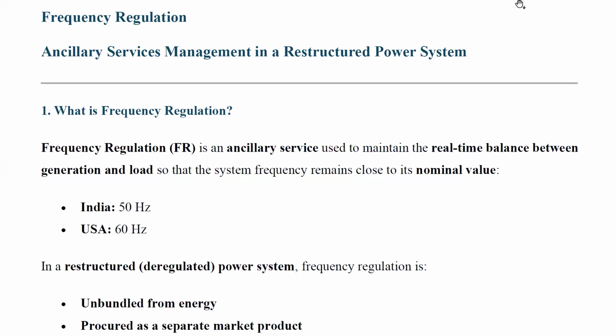Today we are going to see about frequency regulation, which is one of the ancillary service managements in a restructured power system. So, what is meant by frequency regulation? Frequency regulation is an ancillary service that is used to maintain the real-time balance between the generation and the load, so that the frequency remains close to its nominal value. The nominal value of the frequency in India is 50 hertz. In the US and some Western countries, it is 60 hertz.